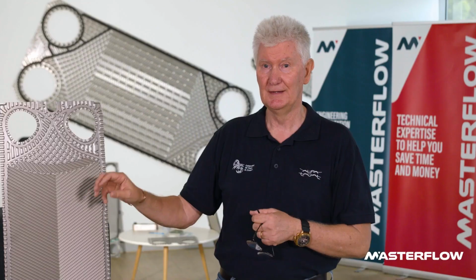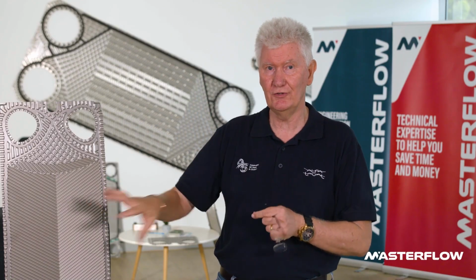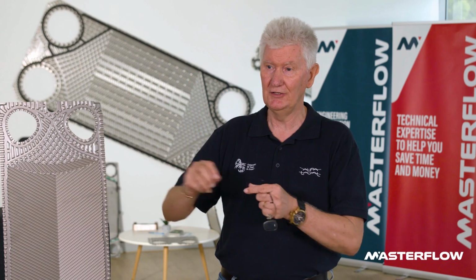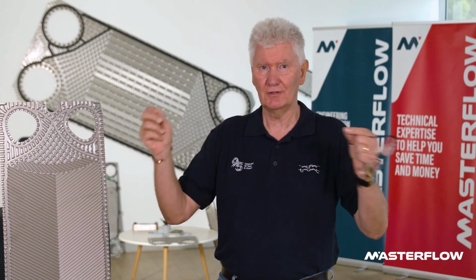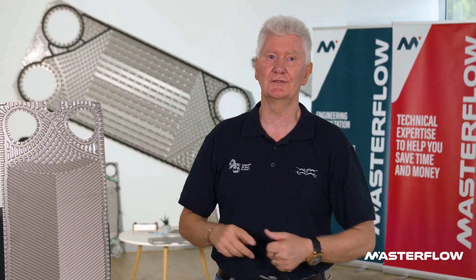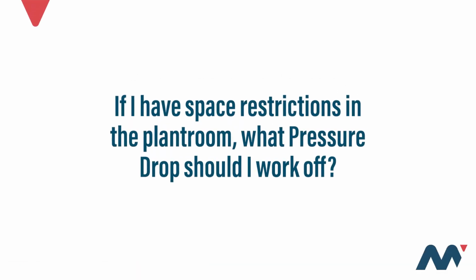Overlapping that, when you start looking at the temperature profile, if the temperature profile is fairly close, like 1 degree, you want a very efficient heat exchanger. And you choose a certain plate geometry to give you that high heat transfer efficiency. But the low pressure drop kind of negates you using that, because that's a high pressure drop plate. You need to use a low pressure drop plate. So again, it's all a case of sacrifice and compromise. That's something you've got to sit down with the contractor or customer and come up with an acceptable design.